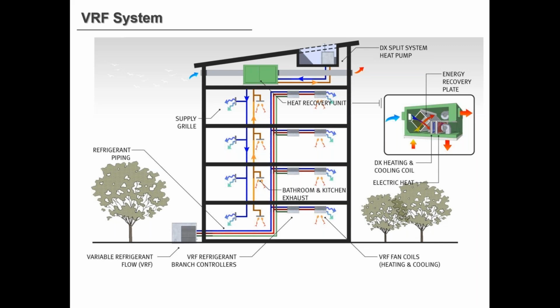So you absolutely can have rooms that are in unoccupied mode with minimum ventilation for pressurization when the students are not in that classroom, be it in an elementary school when they have gym class or a cafeteria during lunch hour, or in the case of high schools, you will see that there's a host of classrooms that don't have homeroom, for example, and there's a host of specialty classrooms such as science, physics, biology, those types of classrooms. We're able to turn those on and ventilate them when we need them and turn down the ventilation when we do not.